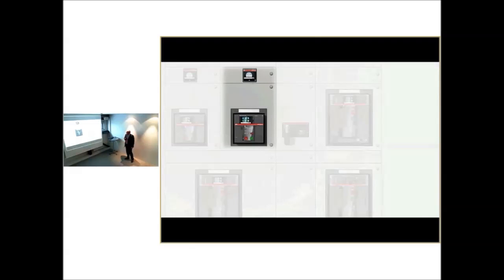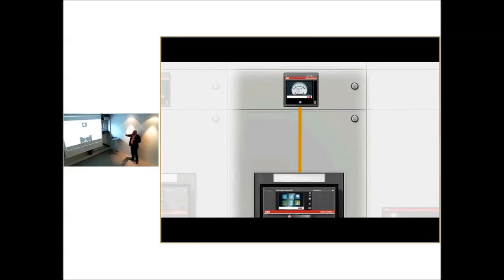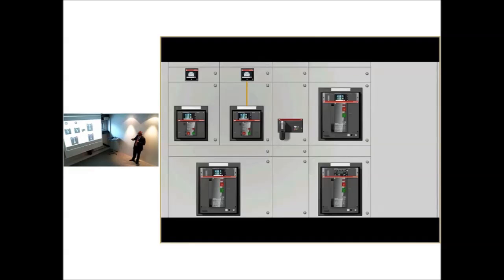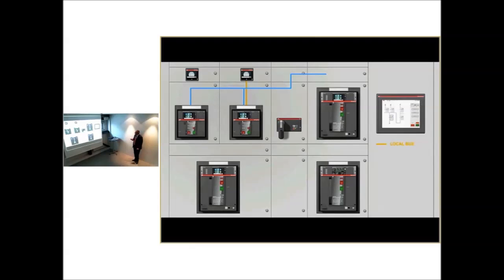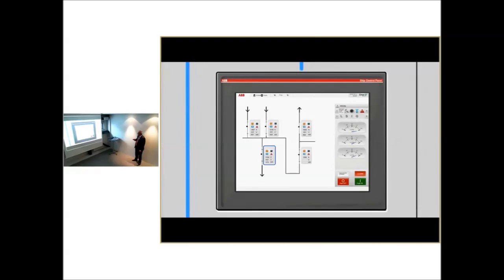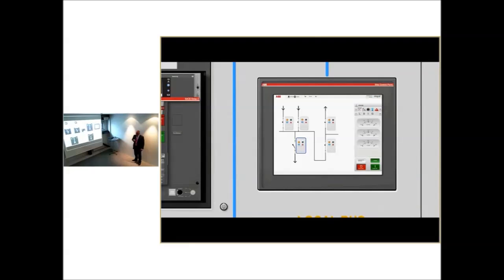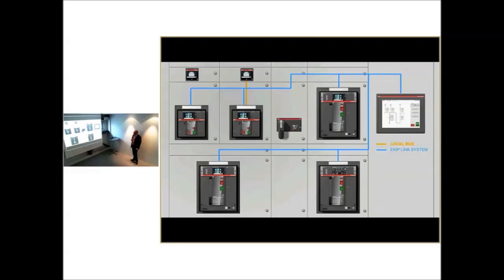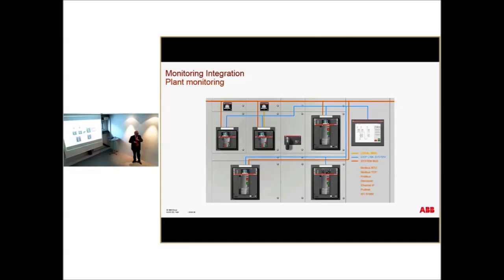This shows exactly the total monitoring, the switch of monitoring, which is exactly the multimeter that I showed before. Then we have the link one, which is the blue. You see all the parameter protections, possibility to open and close, and you have a total monitoring of the plant. You see, this one is exactly what I'm operating. And then the standard communications, taking in consideration the advantage we give that we have independent. This is the only breaker available in the market that gives all independent communication modules, totally.